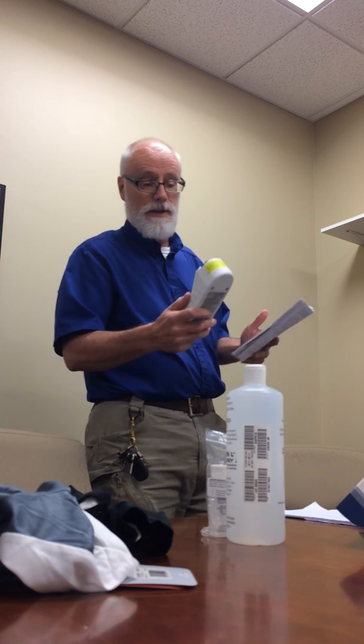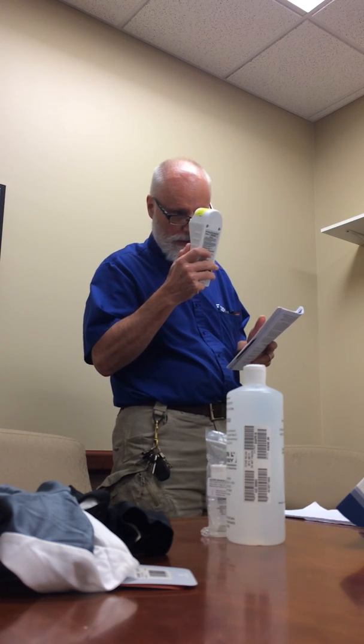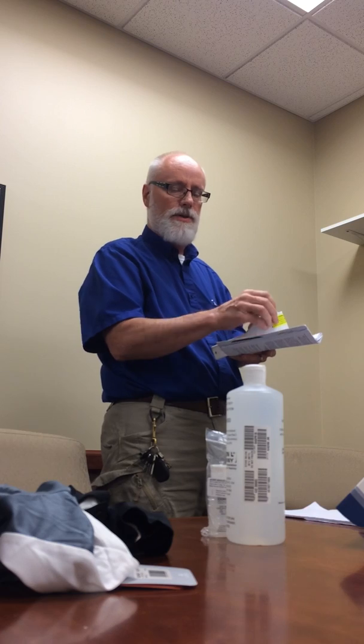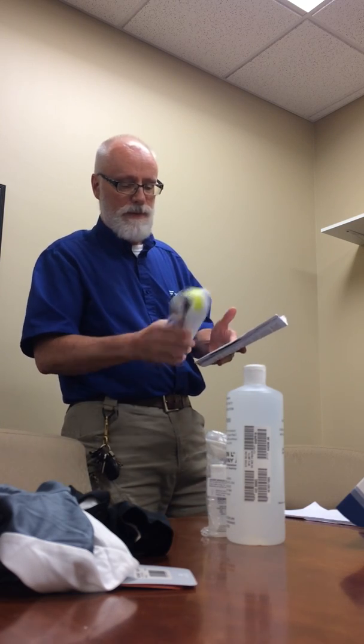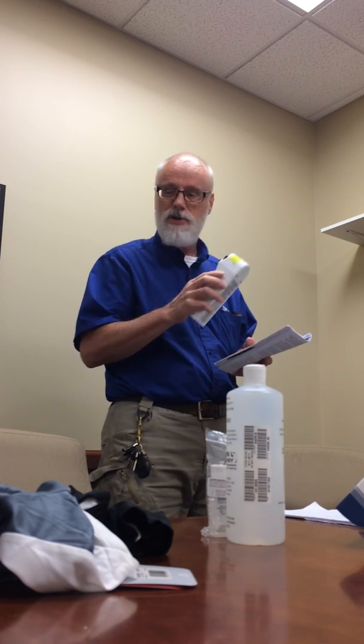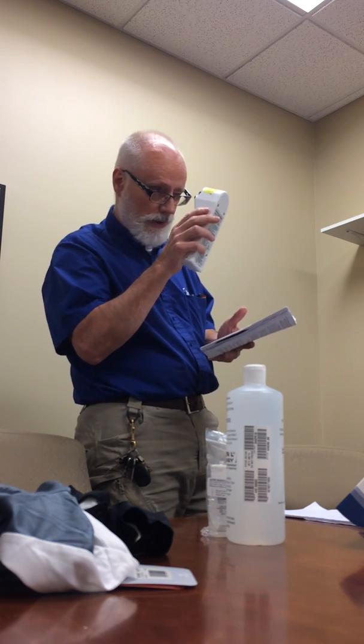On their inspection, it says to visually look into the sensor area to see if there's any crust buildup in there. Also on this side where the sensor is, pop that off, dump the pH solution out. If there's a little crust buildup, the book says to use clean water. I've been telling them to use RO water, flush it out a couple times, and then re-look at it. If there's still buildup, the book says you can use 70% alcohol.